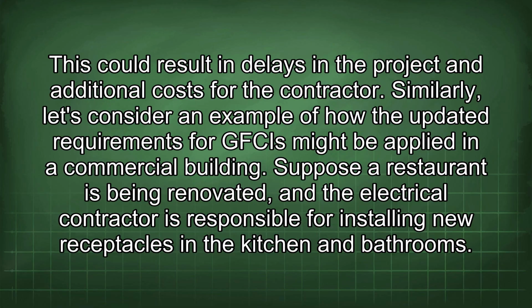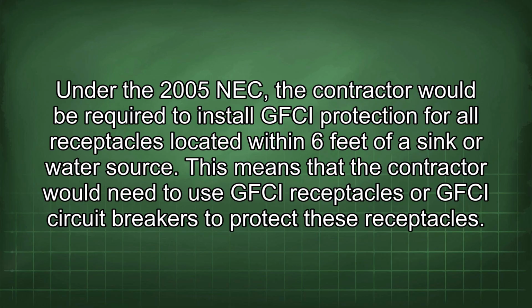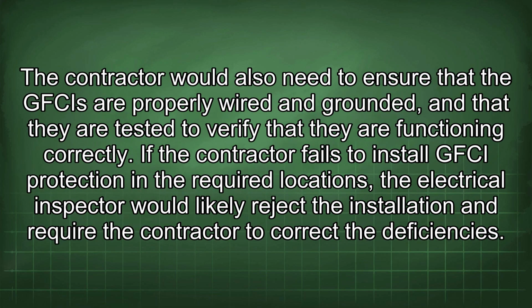Similarly, let's consider an example of how the updated requirements for GFCIs might be applied in a commercial building. Suppose a restaurant is being renovated and the electrical contractor is responsible for installing new receptacles in the kitchen and bathrooms. Under the 2005 NEC, the contractor would be required to install GFCI protection for all receptacles located within 6 feet of a sink or water source. This means that the contractor would need to use GFCI receptacles or GFCI circuit breakers to protect these receptacles. The contractor would also need to ensure that the GFCIs are properly wired and grounded and that they are tested to verify that they are functioning correctly.